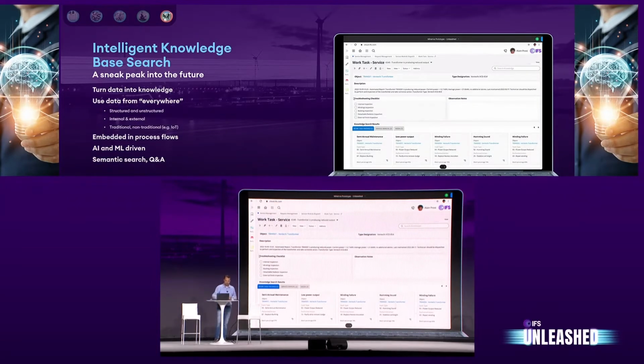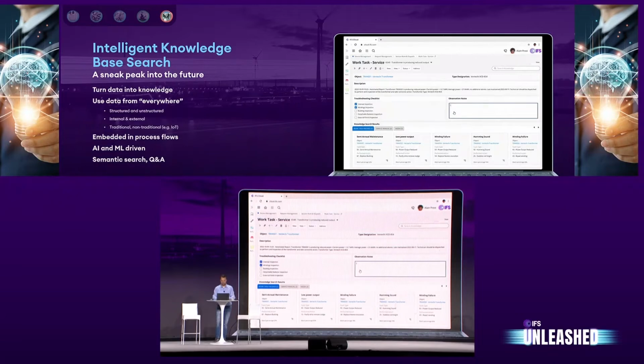But what we also see is that the match percentage, all the way at the bottom, and I realize that might not be visible for everybody, is still quite low. It ranges between 60 and 80% reliability. If I step through my inspection, and as I'm inspecting the windings, I actually notice, as the technician in the field, that I see a flash mark on the core of the turbine. So what I can do, now copy paste this, is add my own observation as an additional data point into my work task.